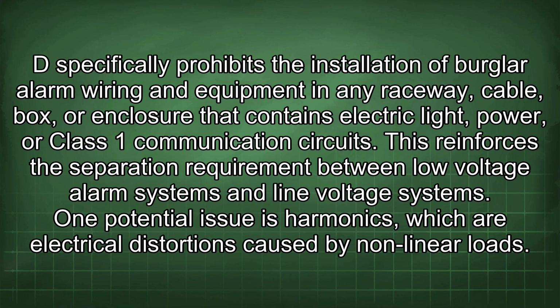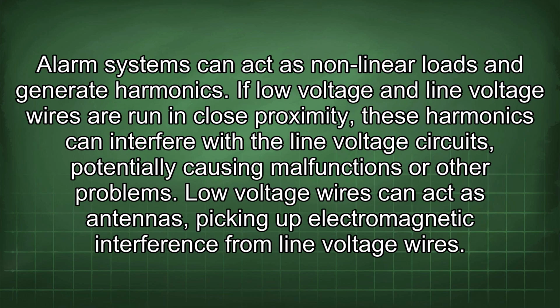One potential issue is harmonics, which are electrical distortions caused by nonlinear loads. Alarm systems can act as nonlinear loads and generate harmonics. If low-voltage and line-voltage wires are run in close proximity, these harmonics can interfere with the line-voltage circuits, potentially causing malfunctions or other problems. Low-voltage wires can act as antennas, picking up electromagnetic interference from line-voltage wires.